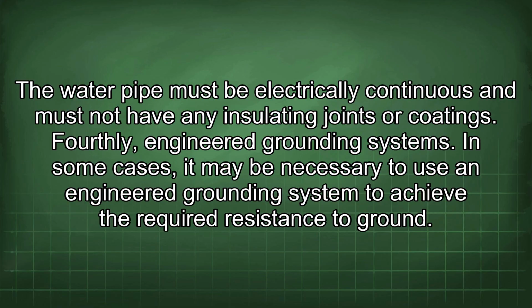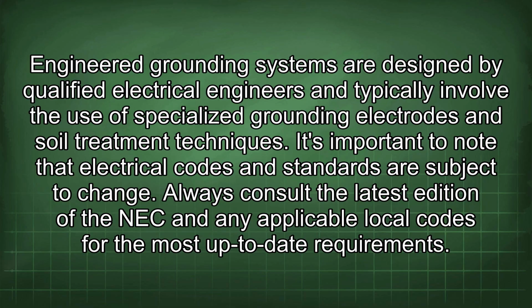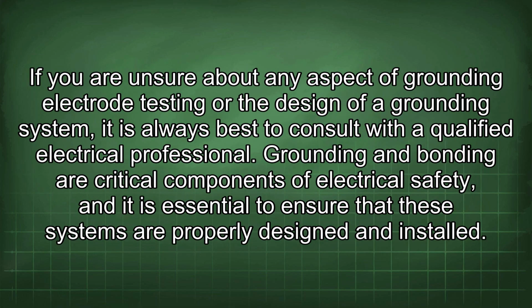Fourthly, engineered grounding systems. In some cases, it may be necessary to use an engineered grounding system to achieve the required resistance to ground. Engineered grounding systems are designed by qualified electrical engineers and typically involve the use of specialized grounding electrodes and soil treatment techniques. It's important to note that electrical codes and standards are subject to change. Always consult the latest edition of the NEC and any applicable local codes for the most up-to-date requirements. If you are unsure about any aspect of grounding electrode testing or the design of a grounding system, it is always best to consult with a qualified electrical professional.